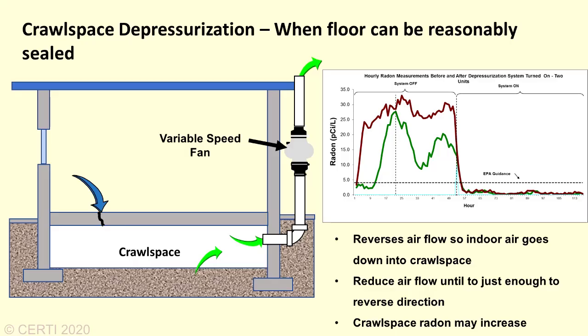This is typically done from within the crawlspace. However, in the case of very low clearances that may be found in older schools, the sealing will need to be done from above. The fans should be variable speed or dampers be installed in the ductwork to reduce the amount of air that is withdrawn to be just enough to create a negative pressure within the crawlspace relative to the occupied space above.